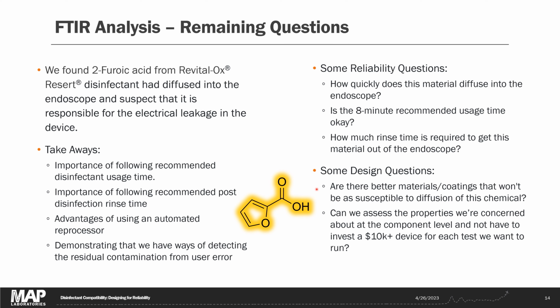On the reliability and design side, we need to be thinking about how quickly does this disinfectant diffuse into the endoscope? Is it going to be okay after a typical 8-minute disinfection? Is our rinse time adequate to get this material out of the endoscope? And then from the design stage, are there better materials we could be using that are less susceptible to diffusion of this chemical? And what kind of test could we use to answer that question? Can we do it at the component level and not have to make a $10,000 plus device each time we want to run a test?